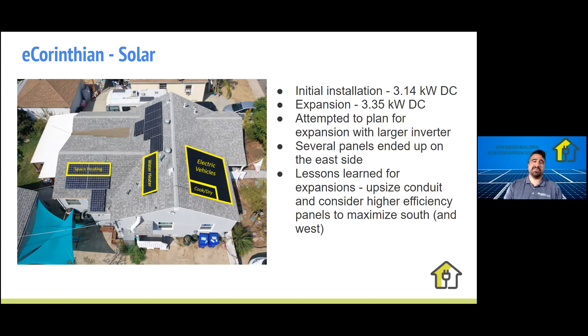Some of the lessons I picked up from this: make sure you're upsizing conduit, because even if your inverter is large, that doesn't mean your conduit is large enough to handle your expansion. You want to have that to avoid rework. Also consider higher efficiency panels, especially if you're thinking about doing expansion in the future. You want to make sure you can maximize as much as you can on the south and potentially the west orientations.